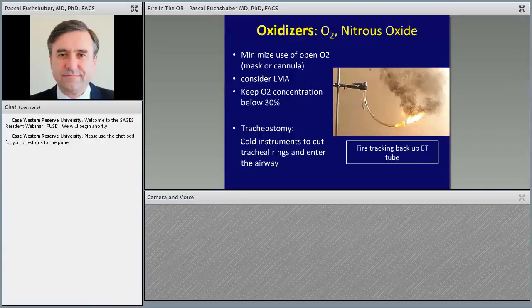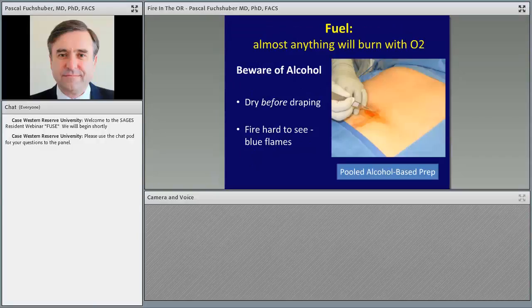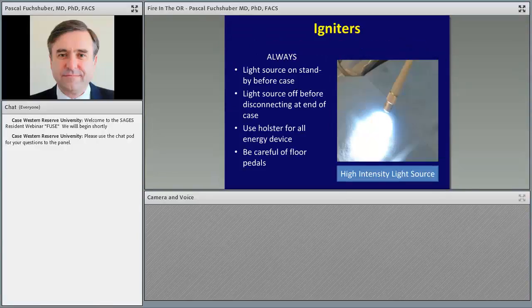And that has consequences of, again, what you're going to do when a fire occurs. Some of it is going to be counterintuitive, but you have to do it to avoid injuries that are lethal to the patient. Fuel, well, as I said earlier, almost anything will burn with O2. So in principle, everything that's in the operating room lying on the patient essentially is a fuel source. But beware especially of alcohol. Make sure it's dry. And remember that alcohol flames are very hard to see.